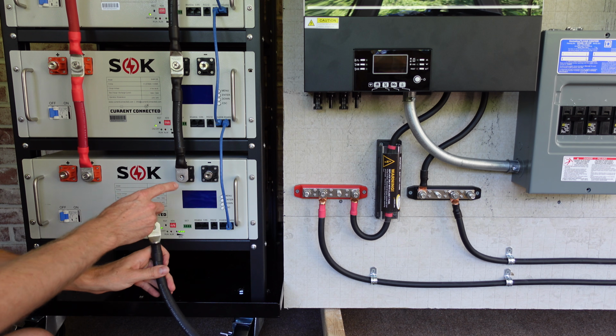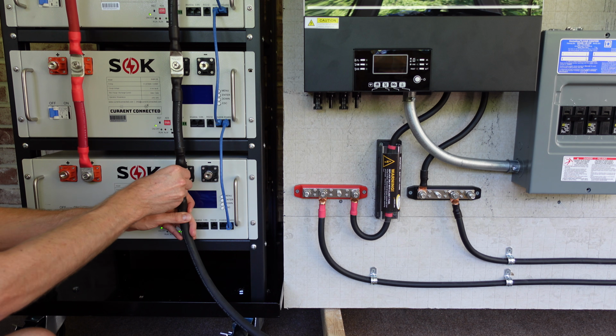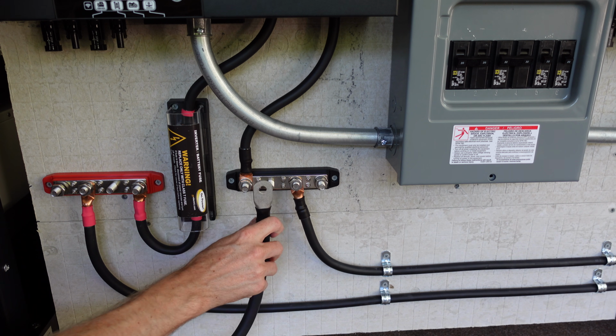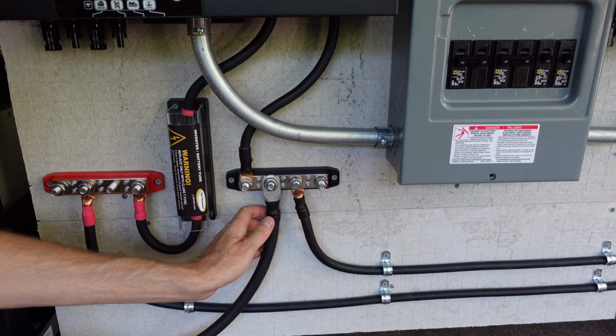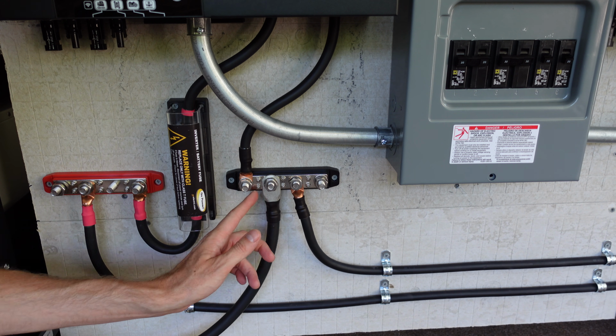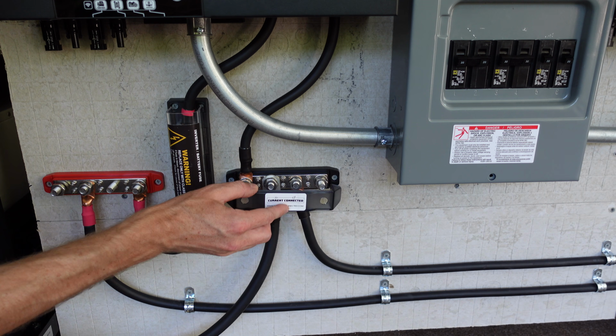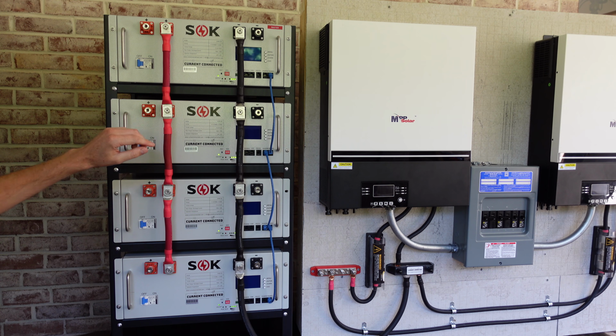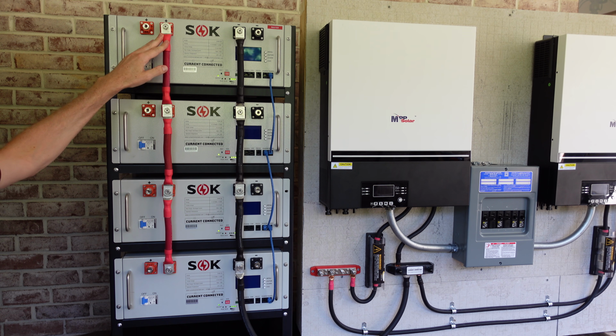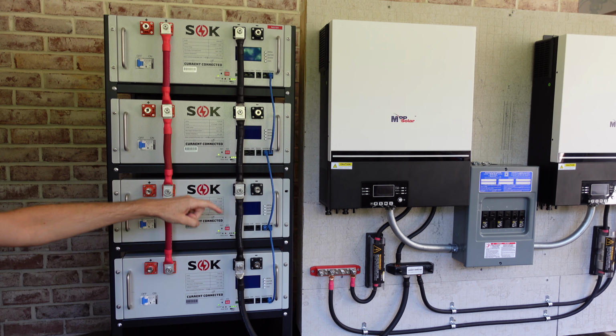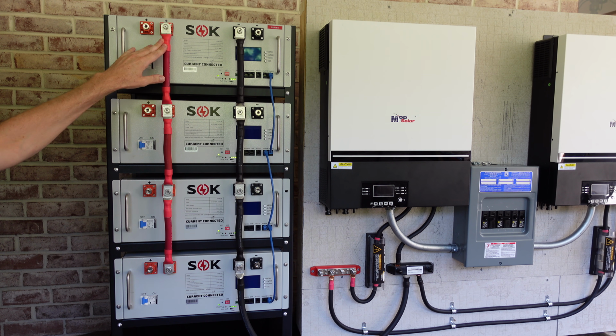So I'll have the negative come off the bottom right of the battery bank. And we're going to connect that to our negative bus bar. And with that connection completed, I've checked the torque of all the bolts on this bus bar. Ready to apply my safety cover. For the positive connection, I'm actually going to connect it to the top left. So we have the negative on the bottom right and the positive on the top left.